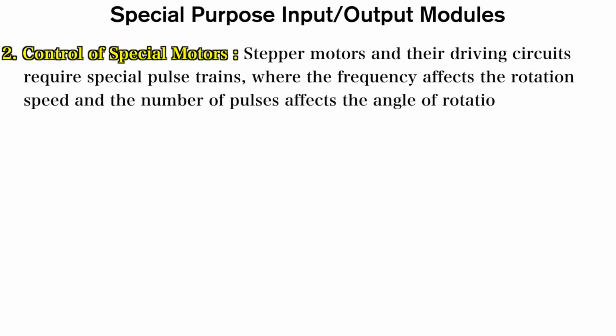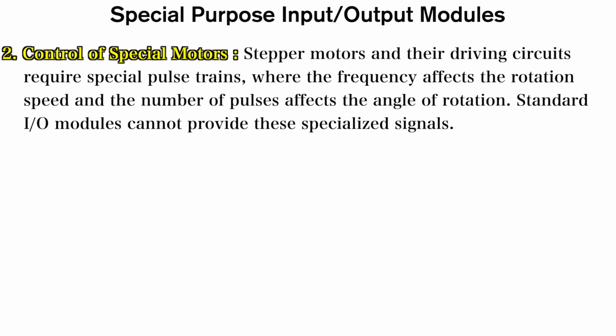Next is the case of special motors. Stepper motors and their driving circuits require special pulse trains, where the frequency affects the rotation speed and the number of pulses affects the angle of rotation. To control these special motors, the standard input or output modules cannot provide these specialized signals. So here we use the specialized input output modules too.